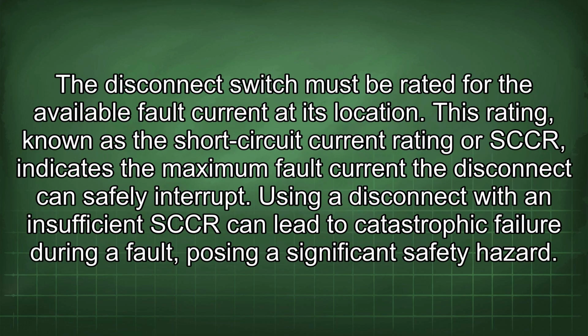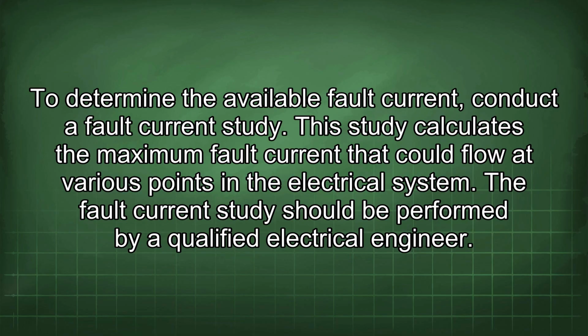The disconnect must be rated for the available fault current at its location. This rating, known as the short circuit current rating or SCCR, indicates the maximum fault current the disconnect can safely interrupt. Using a disconnect with an insufficient SCCR can lead to catastrophic failure during a fault, posing a significant safety hazard. To determine the available fault current, conduct a fault current study.